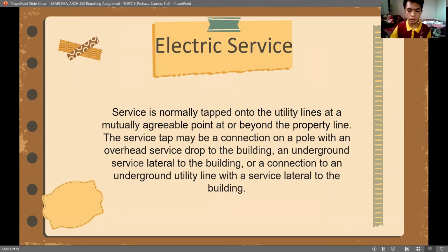First part, electric service. Service is normally tapped into the utility lines at a mutually agreeable point at or beyond the property line. The service tap may be a connection on a pole with an overhead service drop to the building, an underground service lateral to the building, or a connection to an underground utility line with a service lateral to the building.